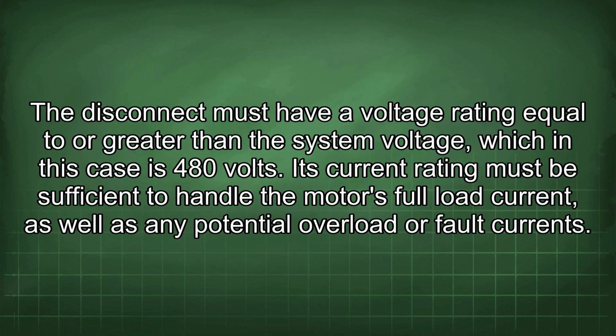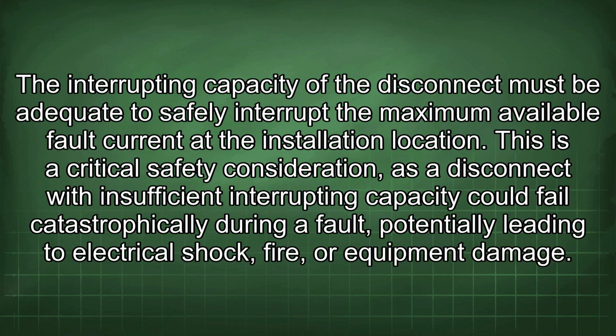The disconnect must have a voltage rating equal to or greater than the system voltage, which in this case is 480 volts. Its current rating must be sufficient to handle the motor's full load current, as well as any potential overload or fault currents. The interrupting capacity of the disconnect must be adequate to safely interrupt the maximum available fault current at the installation location. This is a critical safety consideration, as a disconnect with insufficient interrupting capacity could fail catastrophically during a fault, potentially leading to electrical shock, fire, or equipment damage.